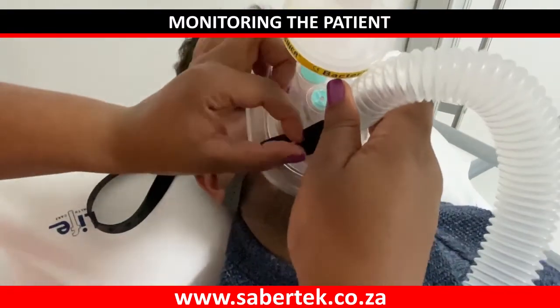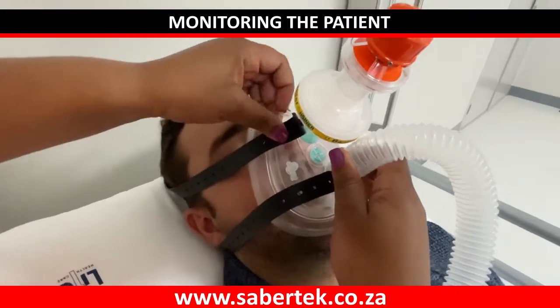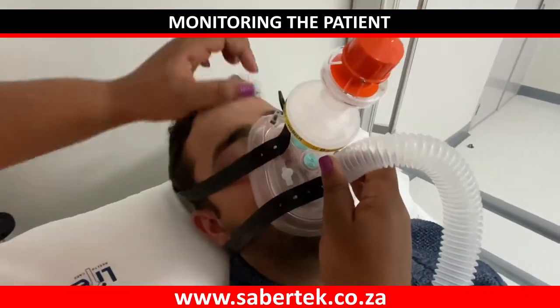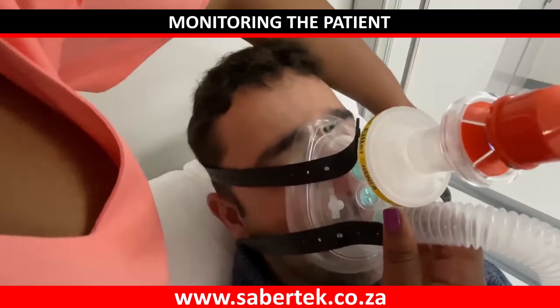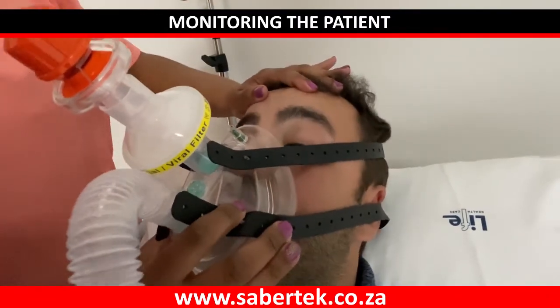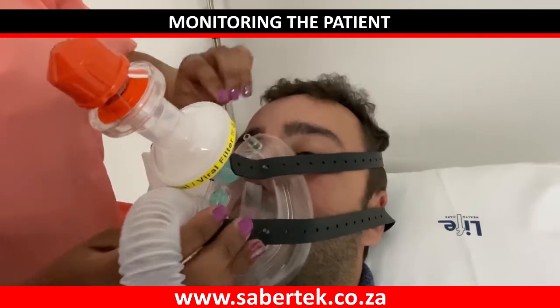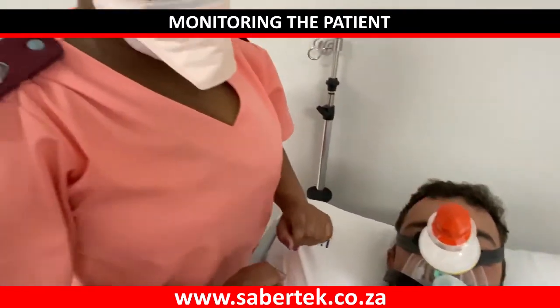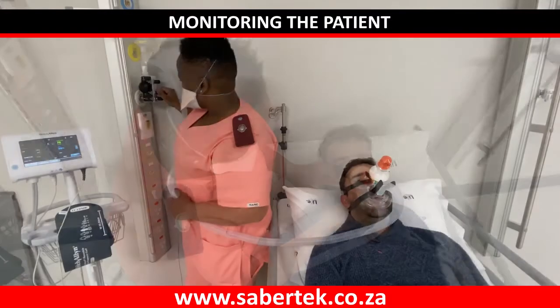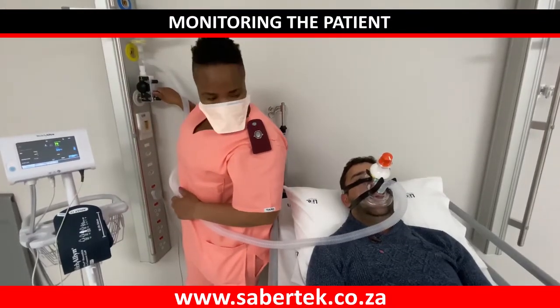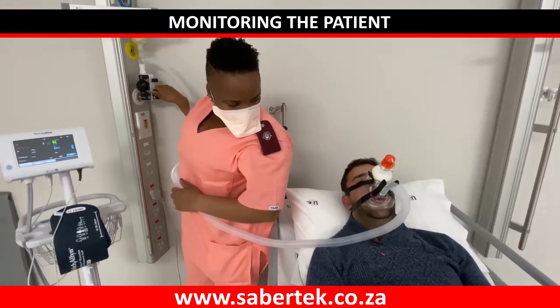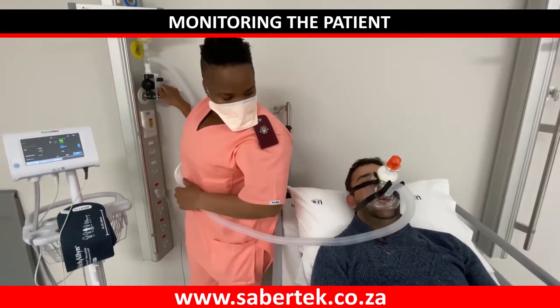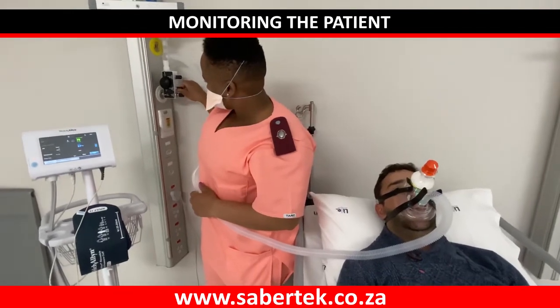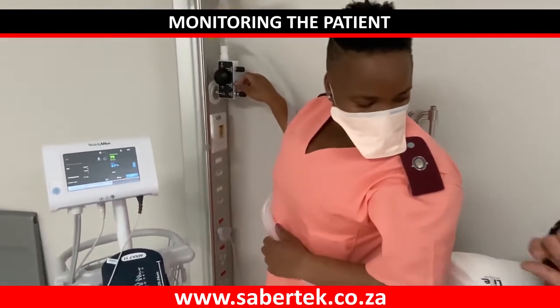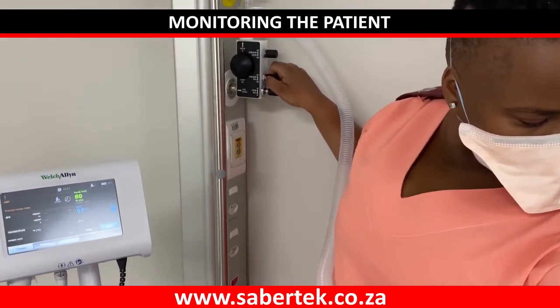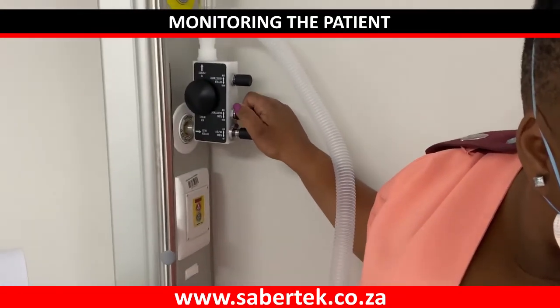The following must be checked while the patient is on CPAP therapy. Any patient attached to the CPAP device also always needs to be attached to an oxygen saturation device. A drop to 85% or lower needs to be reported to the attending clinician immediately and documented. Check that the PEEP valve remains open during inspiration to ensure that the generator supplies adequate flow to meet the patient's requirements. A small amount of air flowing from the exit of the PEEP valve indicates adequate flow to meet the patient's requirements. Note that the markings on the PEEP valve become relative at high flow rates.